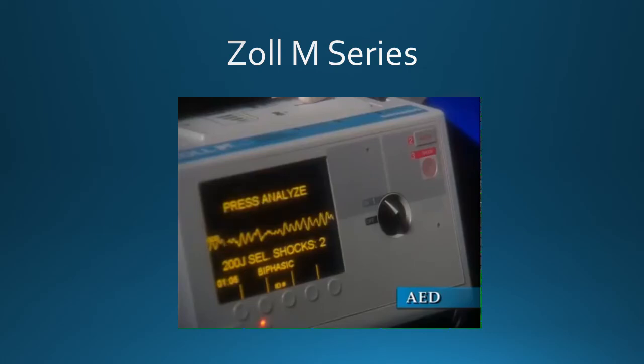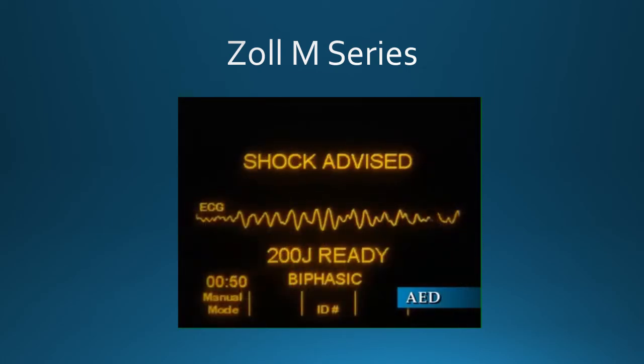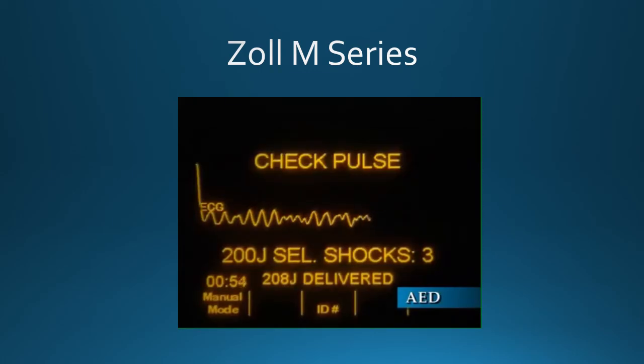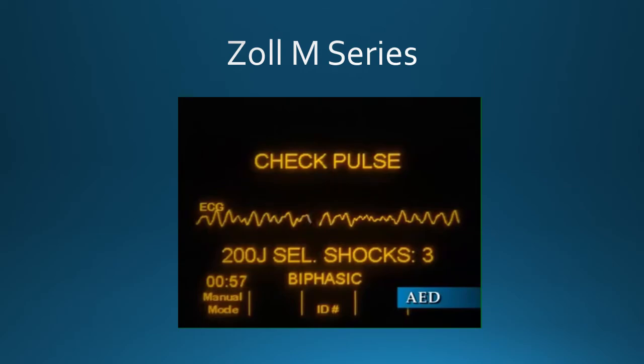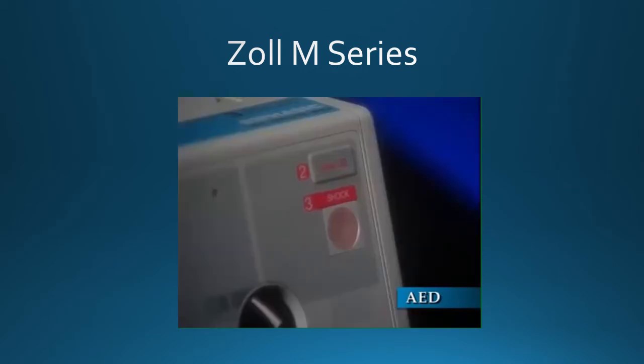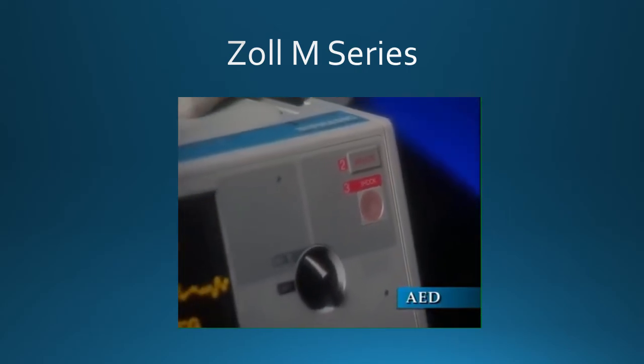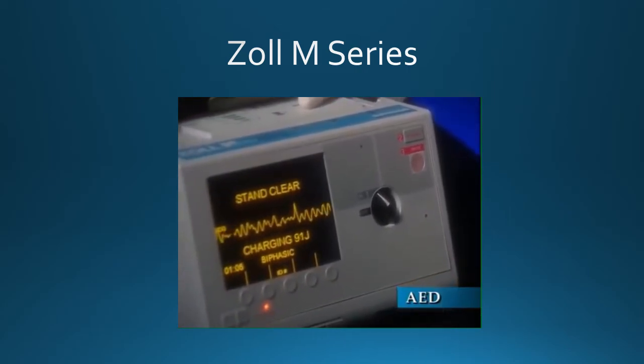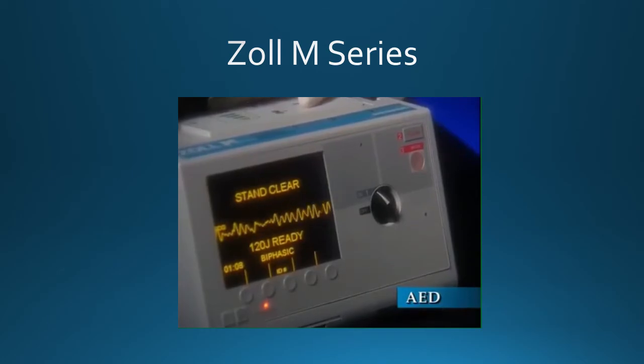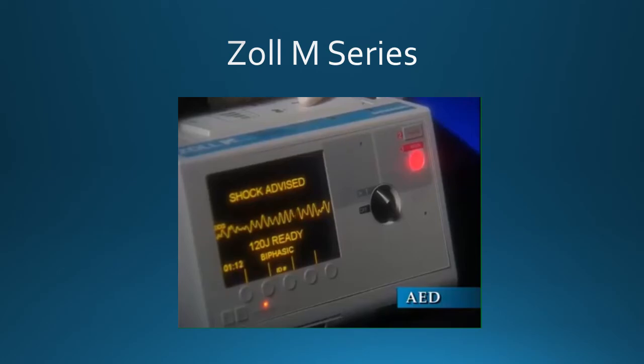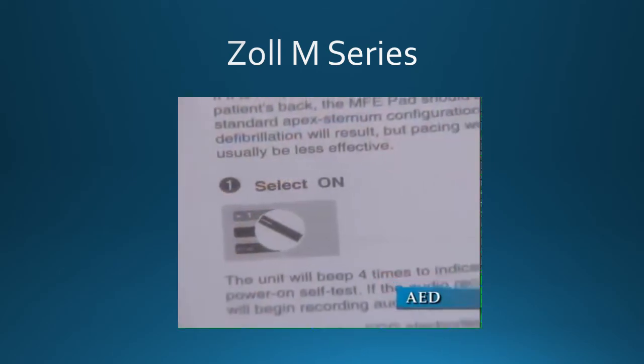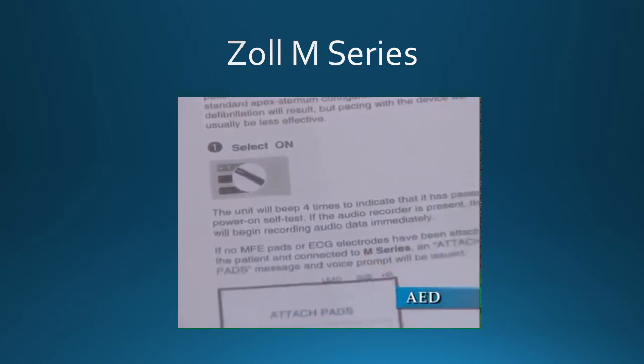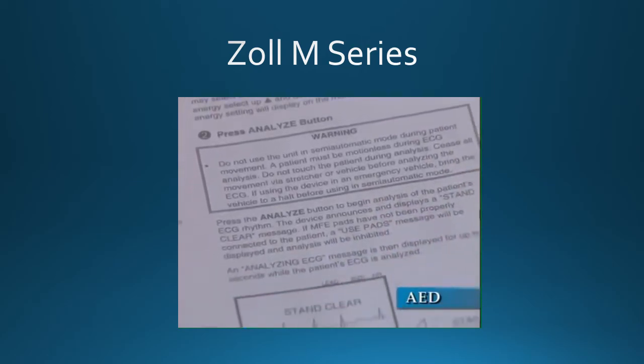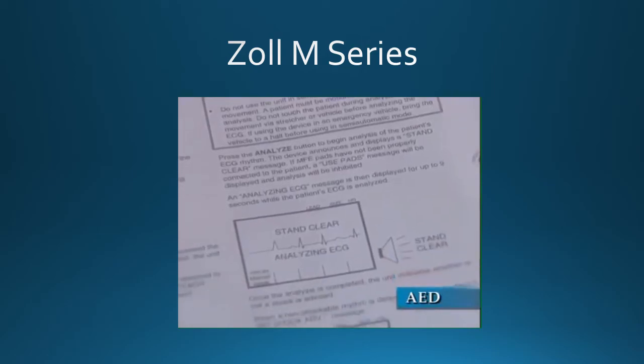Press analyze. Press shock. After the shock, check pulse. The display returns to the energy selected and indicates the number of shocks delivered to the patient. Press the Analyze button to restart an ECG analysis and determine if additional shocks are required. If so configured, the M-series will automatically analyze and recharge. The unit uses both audio and visual prompts to present critical information to operators. Please consult the M-series Operator's Guide for detailed information on voice prompts and operating messages, which can occur during semi-automatic operation. If your device has been custom configured, some information may be different.